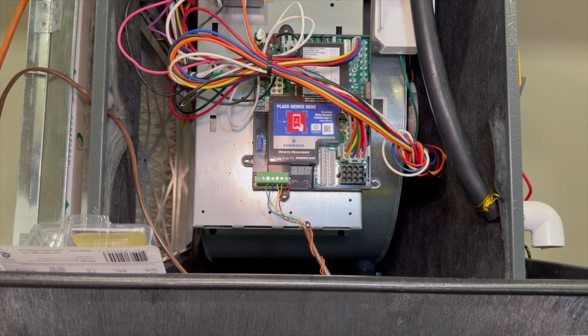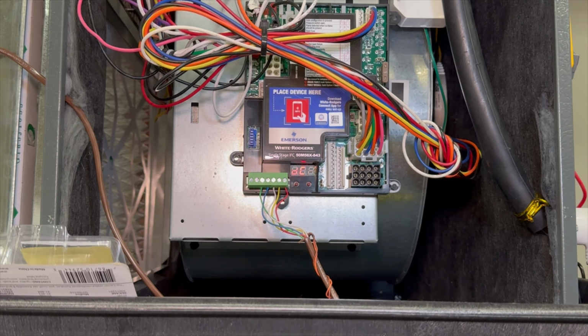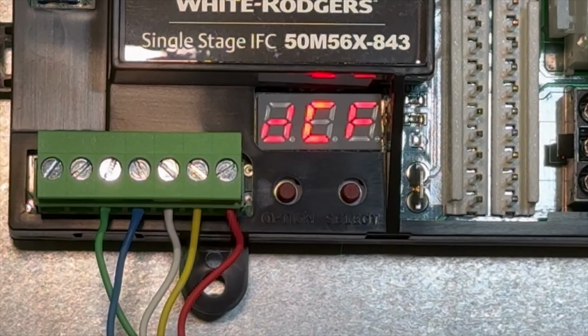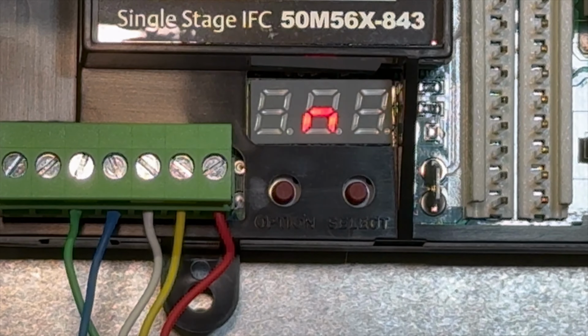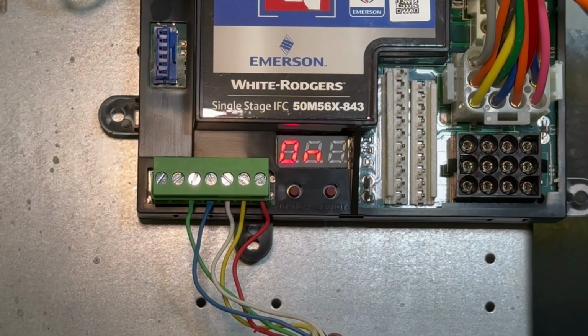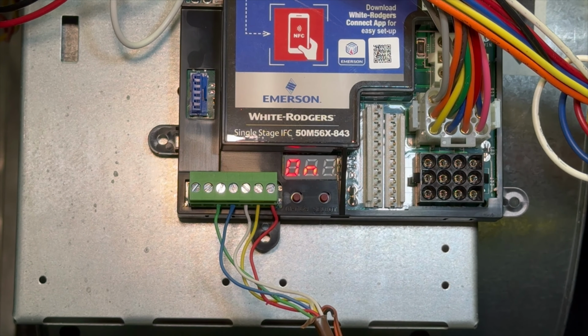During initial power up, when you first send power to the control, it will go through the auto harness configuration test, in which it will actually test the limit circuit first, then the igniter, then the inducer, finally the pressure switch, and once the pressure switch circuit is closed, the control knows exactly which furnace it has been installed in. Now this auto harness configuration will occur twice, once when you first power it up, and then when you remove your door switch and take the power off and close the furnace up getting ready to leave, you power it up the second time, and after that second test it will lock that harness configuration in.